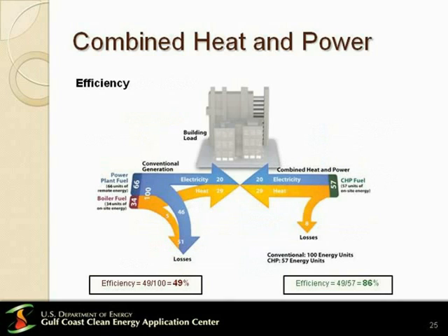Now why is it efficient? Consider this imaginary building, which requires 49 units of energy. The power plant fuel required to produce 20 units of electricity is actually 66 units of power plant fuel, because all the heat in the power plant is just emanated into the atmosphere. When you add in transmission and line losses, the net electricity that arrives on site is extremely inefficient. In this example, the CHP system, to provide the same 49 units of energy, consumes only 57 units of CHP fuel. As a result, the efficiency in this example is about 86%, compared to conventional generation, which is in the 49% range.